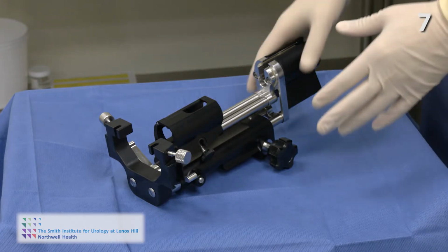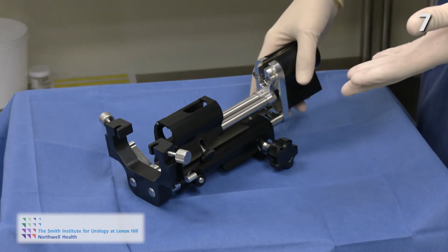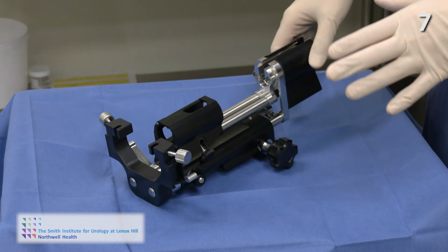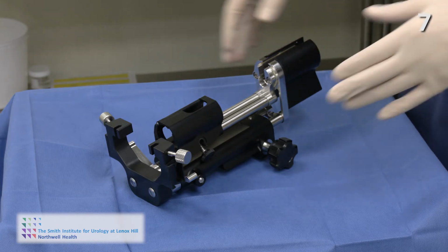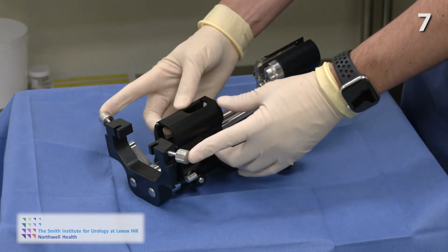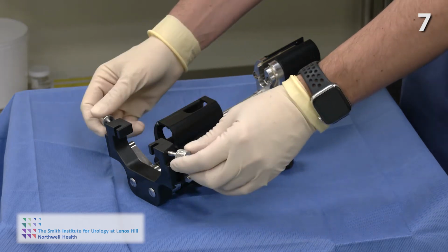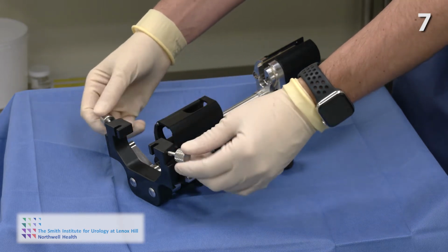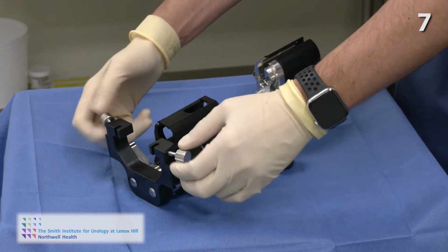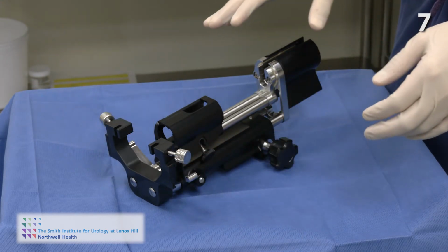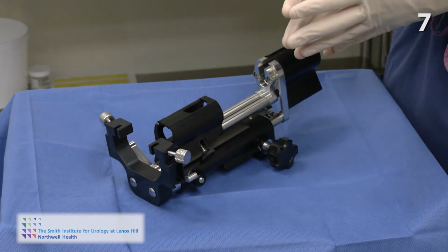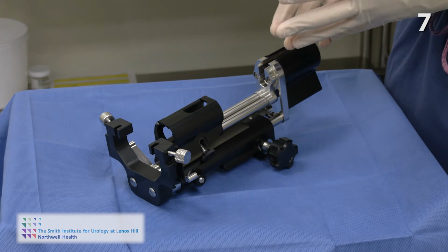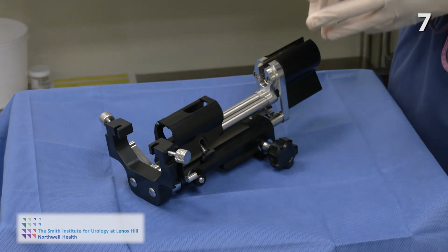This is the stepper. This is what the ultrasound probe is attached to. This is one of the most common areas pieces are missing from. Just an example, notice that these screws are not the same because we've lost screws in the past. They all reverse thread, so to tighten them, they go towards you. At the end of the case, you spray this down with the enzymatic cleaner and send this down to your sterile supply for whatever processing you're doing at your institution.